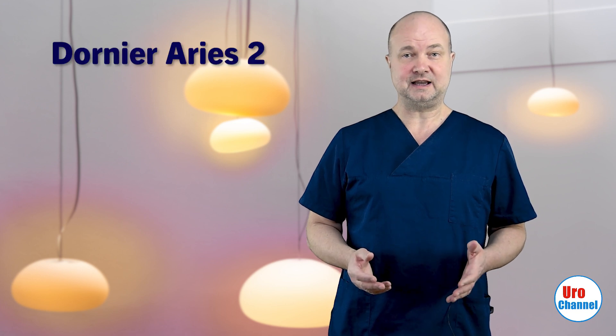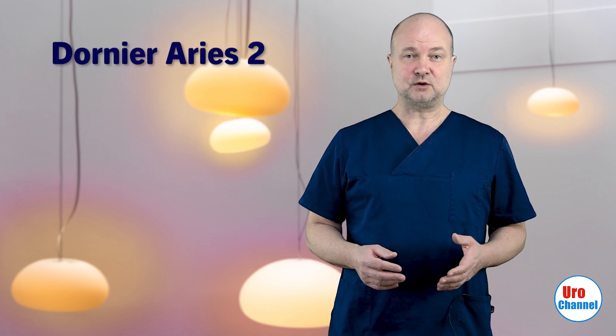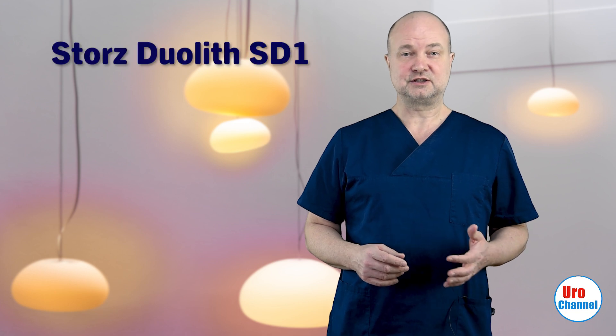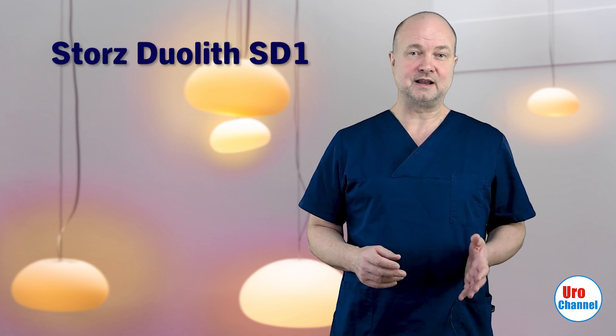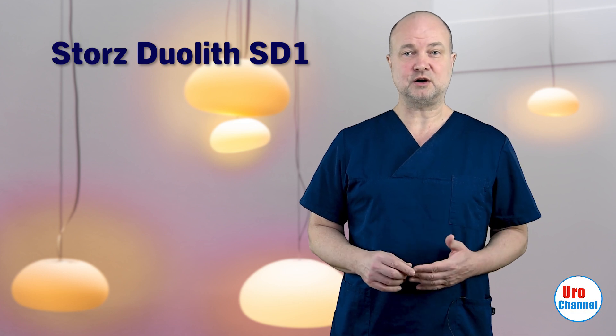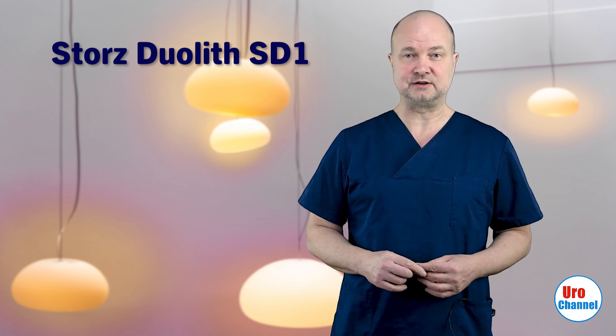My device is a Dornier Aries 2. The mode of shockwave generation is electromagnetic. To my knowledge, the Aries is not approved in the US. But if you are watching from the States, the Storz Duolith SD1 has FDA approval — this is also a machine with focused shockwaves from an electromagnetic generator. I am not getting paid by any of these companies to say this.